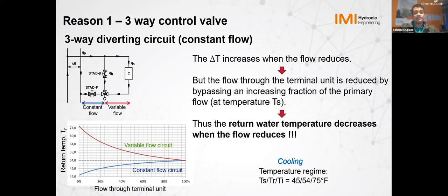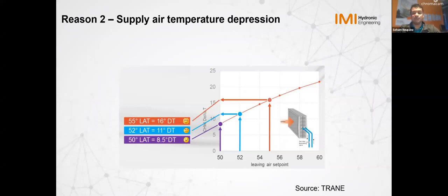So moving on, the second reason that causes your delta T issue is supply temperature depression. What happens, especially with the maintenance people on site, is that when we're not able to get the room temperature quickly, people just tend to switch the set point. So you lower the set point. Initially the system was designed with a 55-degree leaving air temperature and 16-degree delta T. But as we keep lowering that set point, from 55 down to 52 and 50, you see a big change in your delta T values. So as we change the set point, the delta T on your chiller is also getting affected at the same point.